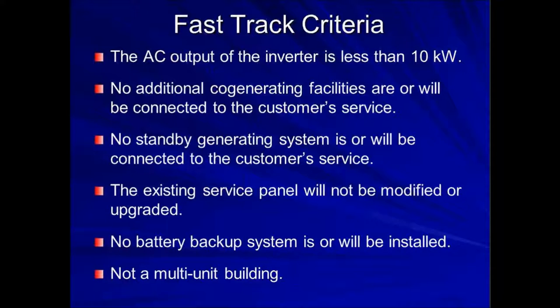So the fast track criteria: the AC output of the inverter is less than 10 kW, no additional cogeneration facilities are there or will be there, no standby generation system is or will be connected to the customer service, the existing service panel will not be modified or upgraded, no battery backup system is or will be installed, and this is not a multi-unit building.